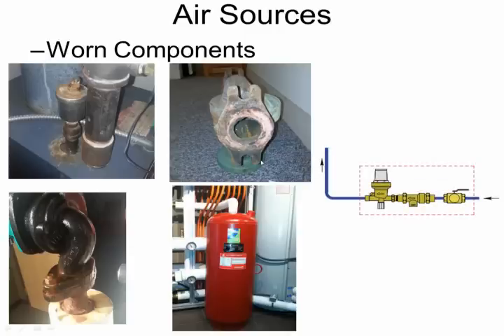Now what happens when that water leaks out? Well, the system's going to want to lose pressure, right? But the makeup system is going to make sure the pressure stays up. So as your makeup system works, the water from the source of that makeup is typically laden with what? Air. And it's another source of getting air into the system. To do what? Create the problems that we've been talking about. I show an expansion tank right here. As that expansion tank starts to age, that bladder starts to wear, starts to become what's called waterlogged.